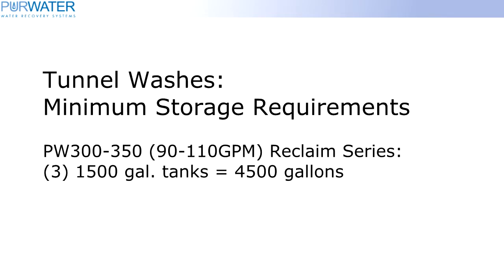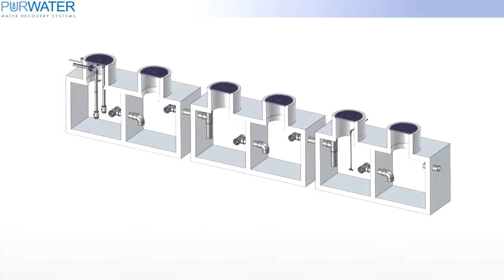For tunnel washes, using a PW300 or PW350, we would require a minimum of 4,500 gallons, which can be achieved by using three 1,500-gallon tanks. For a three-tank setup, the only difference between a two-tank and a three-tank setup is one tank is added to the middle. The recirculation line for a three-tank would be like the two-tank setup, with the line plumbed to the first tank, second chamber.